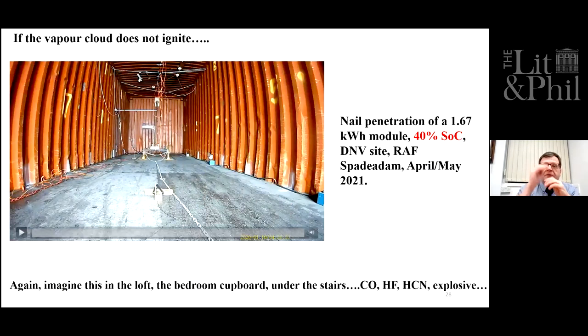Now, if the vapor cloud doesn't ignite, what happens? This was an experiment where we were trying to detonate a vapor cloud explosion, so various squibs were going to go off. But as it turns out, we were below the lower explosion limit, which is about 6 to 11% for the gases from lithium-ion batteries. We had discovered that if we only partly charged these modules up to 40%, ignition was either delayed or didn't take place at all.